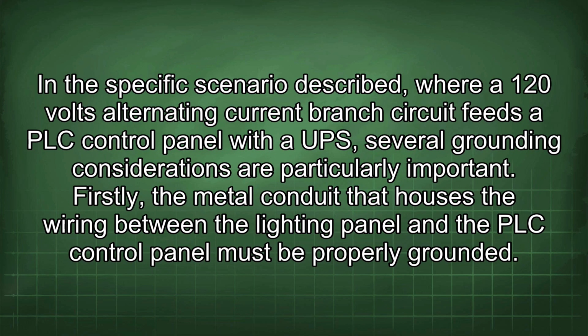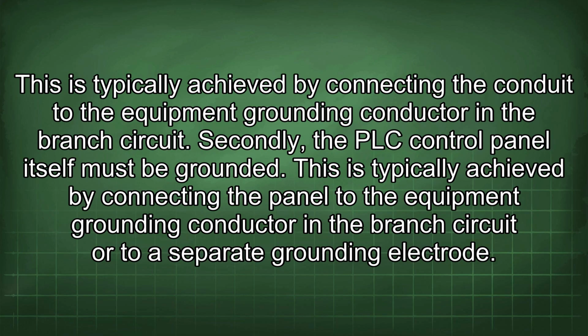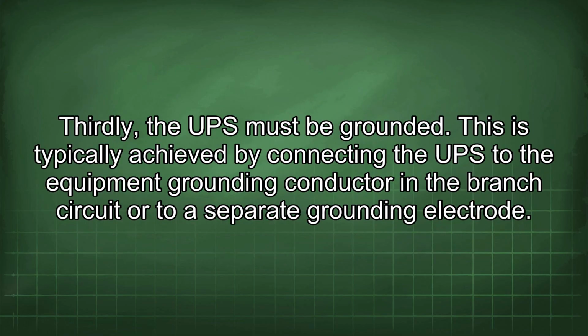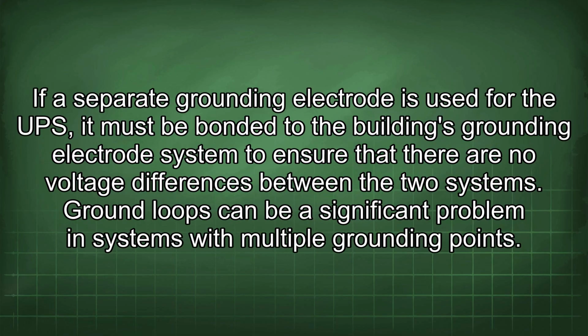Firstly, the metal conduit that houses the wiring between the lighting panel and the PLC control panel must be properly grounded. This is typically achieved by connecting the conduit to the equipment grounding conductor in the branch circuit. Secondly, the PLC control panel itself must be grounded. This is typically achieved by connecting the panel to the equipment grounding conductor in the branch circuit or to a separate grounding electrode. Thirdly, the UPS must be grounded. This is typically achieved by connecting the UPS to the equipment grounding conductor in the branch circuit or to a separate grounding electrode. If a separate grounding electrode is used for the UPS, it must be bonded to the building's grounding electrode system to ensure that there are no voltage differences between the two systems.